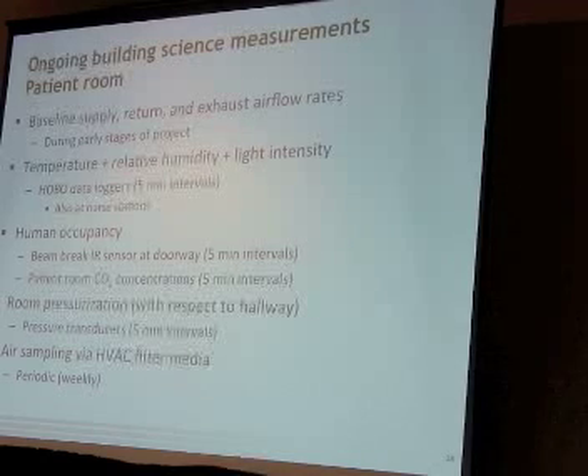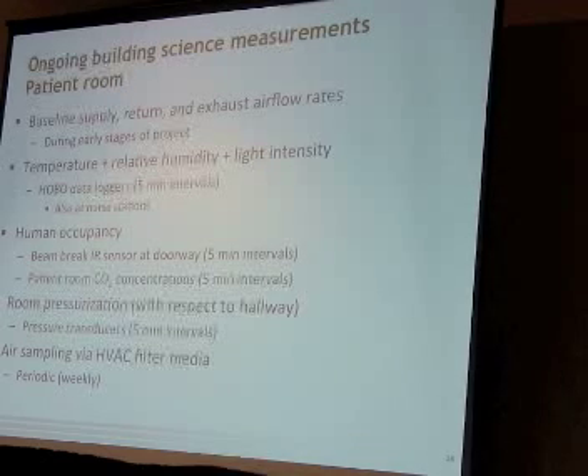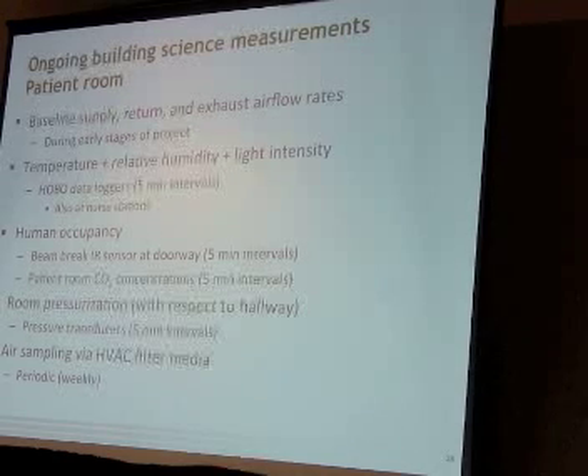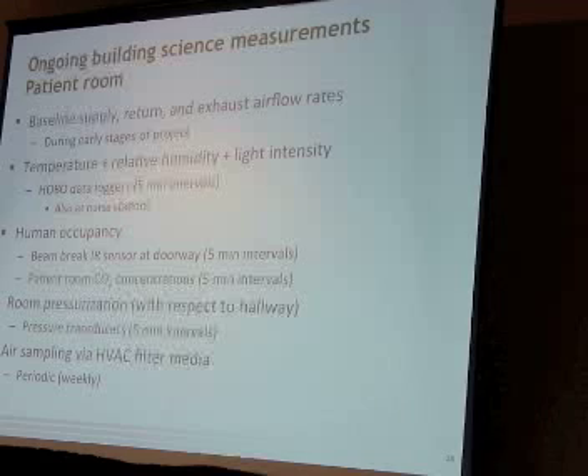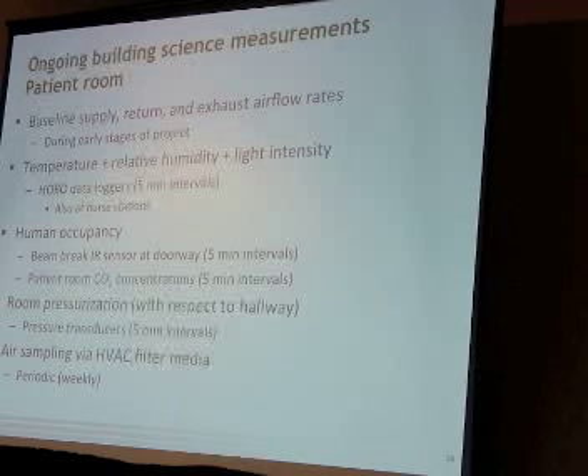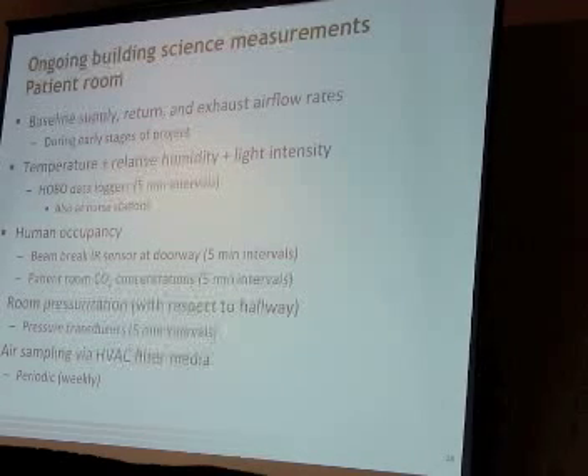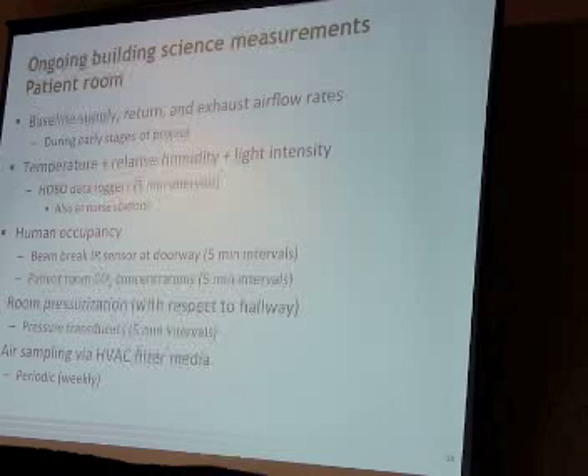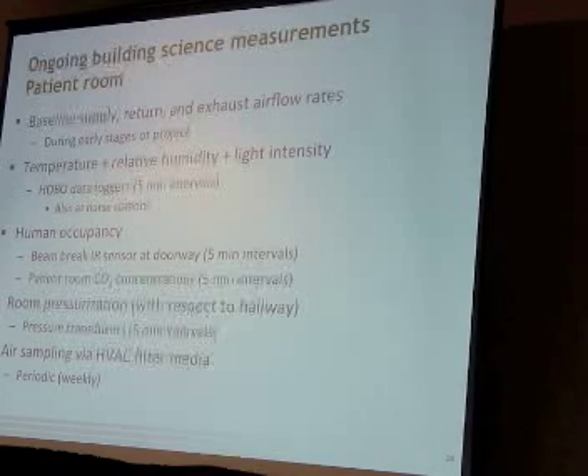So now that we have those at 5-minute intervals for both floors, we also have a bunch of ongoing building science measurements in the patient rooms themselves. This started with some basic baseline supply, return, and exhaust airflow rate characterization. If you look up above you, we were just measuring flow into and out of the room by the mechanical systems, done in the early stages of the project.